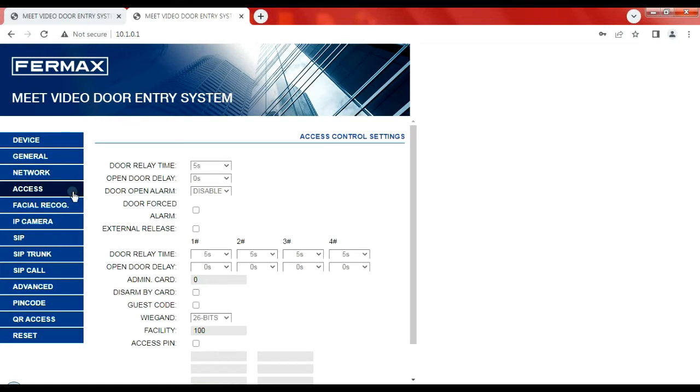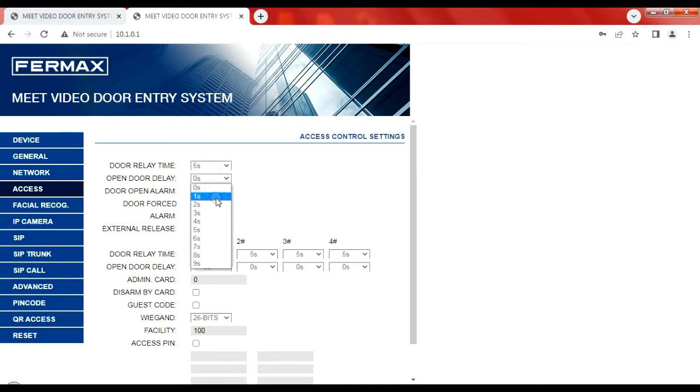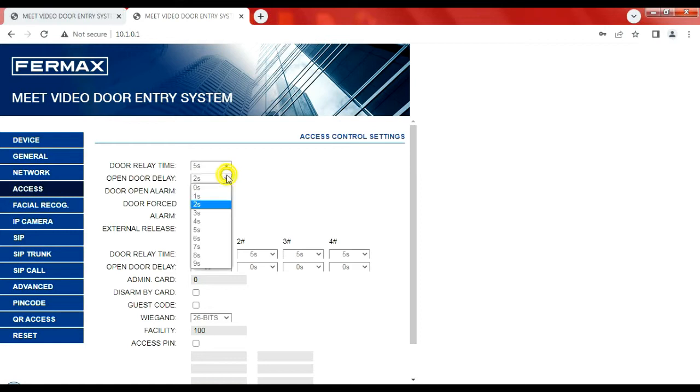Then we come to the access tab. It is actually set for three seconds, this thing, which I don't think is long enough. So I changed that to five. Door open delay. So if you've got a situation, for instance, where you've got the door station, and it's a little distance away from the door, that five second lock release time might be too short. So it's still giving five seconds to get to open the door, but maybe put a little delay in there. So when you press the lock release button on the handset, it doesn't release the door straight away. It could put a little delay, maybe a two second delay after you press the button, then the door will time for five seconds. So that's useful in places where you've got automatic gates, for instance. People might sometimes take off the seatbelt and lean through the window or open the door to use the intercom. It might be the instance where you don't want them to open straight away.